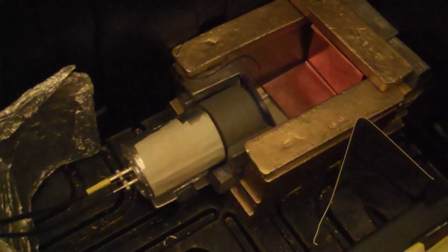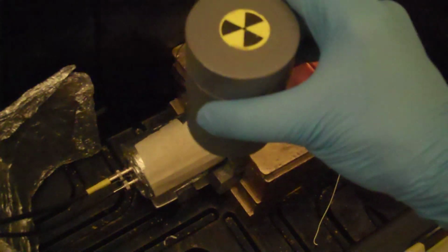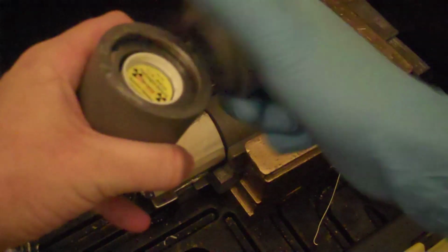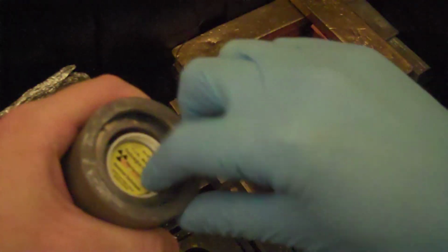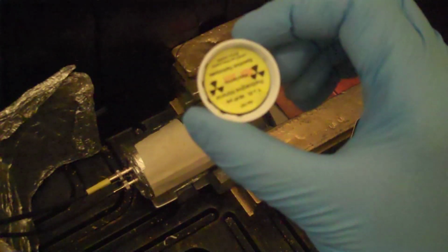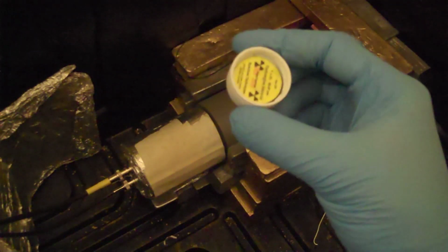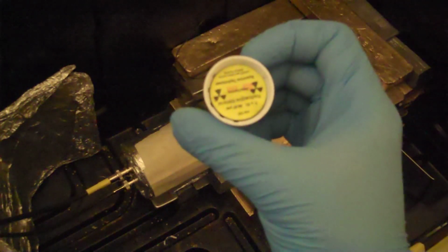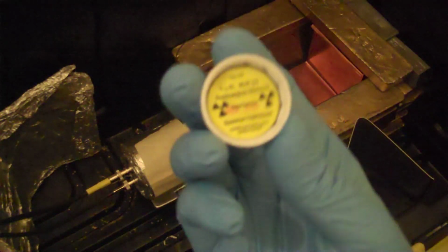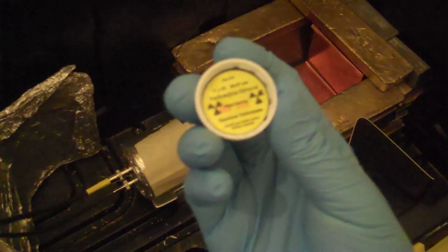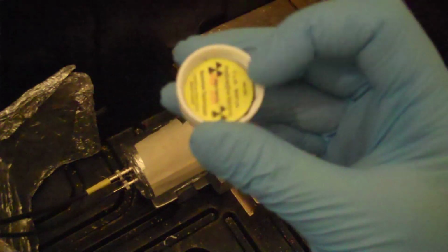Now, before we can use this device, we have to calibrate it. To calibrate it, we need a source. Now, here is a standard source. You might be wondering, why is this inside of a bottle cap? I found that a bottle cap that's been thoroughly cleaned and sterilized allows me to hold this significantly more easily than when it's not. Because in the gloves, these little chips can fall.